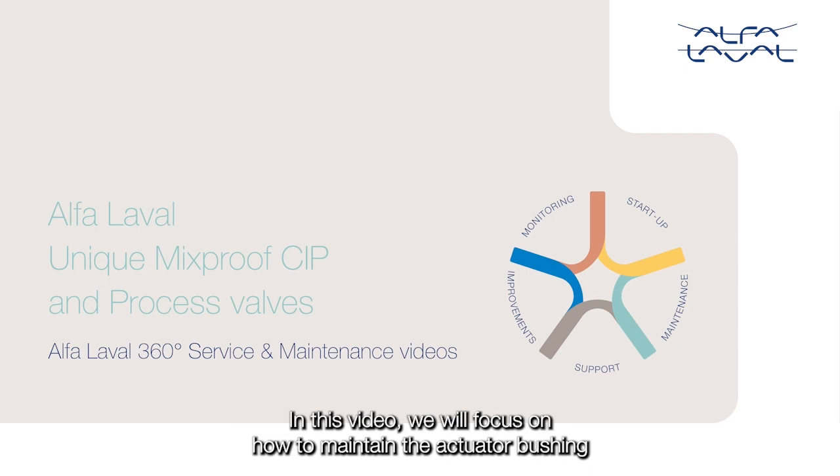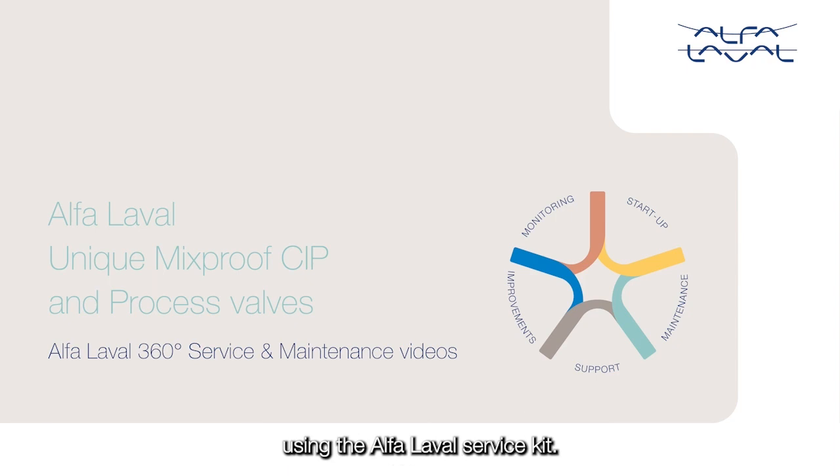In this video, we will focus on how to maintain the actuator bushing in the Alfa Laval unique mix-proof CIP and process valves using the Alfa Laval service kit. Whenever possible, demount the valve from the pipeline before dismantling any parts.